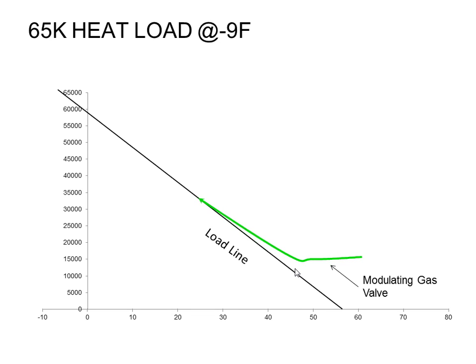The third time that the gas valve would actually close all the way and shut off would be for night setback. So basically a set point change that's initiated by your time clock. If the system is 72 in the day, and at night you like it to be 65 when you're sleeping, great. 11 p.m. comes, the stat switches from 72 to 65, and it does the same thing. It ramps down all the way to 40%, and it says, gosh, I'm still like 6.5 degrees too warm. I'm going to go ahead and shut off. And it'll shut off for a few hours till 1, 2 in the morning, whenever that house becomes 65.